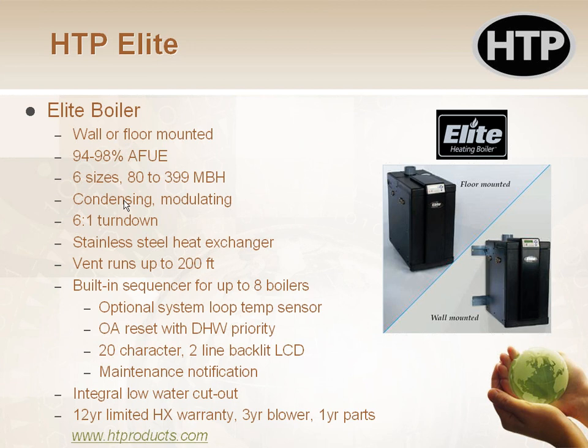In this case, the modulation is a 6-to-1 turn down. If you're not familiar with the term turn down, you can think of it a little differently. If I have a 10-to-1 turn down boiler, that means I can modulate from 100% all the way down to 10%. If I have a 5-to-1 turn down, I can modulate from 100% down to 1/5 of that, which is 20%. And in this case, I have a 6-to-1 turn down, so I can go from 100% down to 16 or 17%, whatever the math works out to.